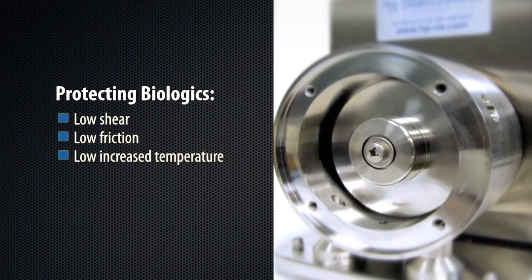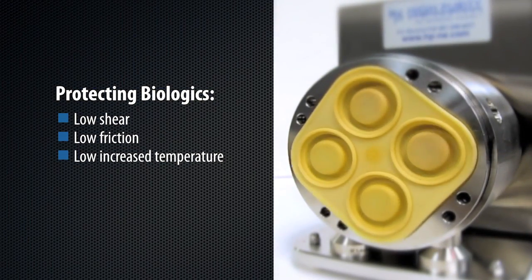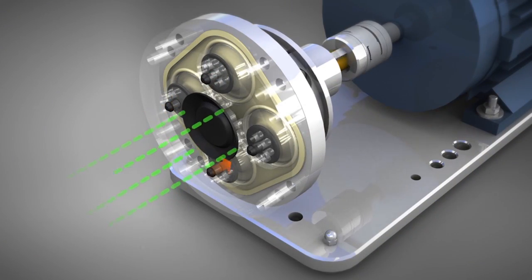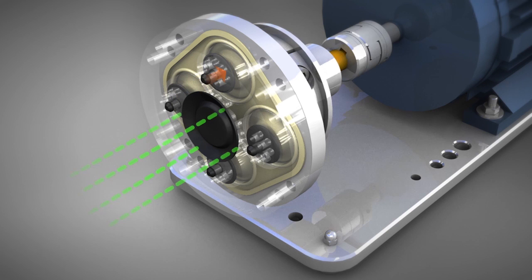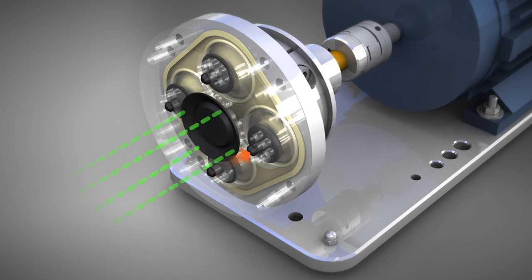Here, you can see how the Quattroflow pump creates a gentle circular movement for each of the diaphragms. As each diaphragm expands, it gently pushes fluid through the valve, which acts like a heart valve. Fluid only goes one way.